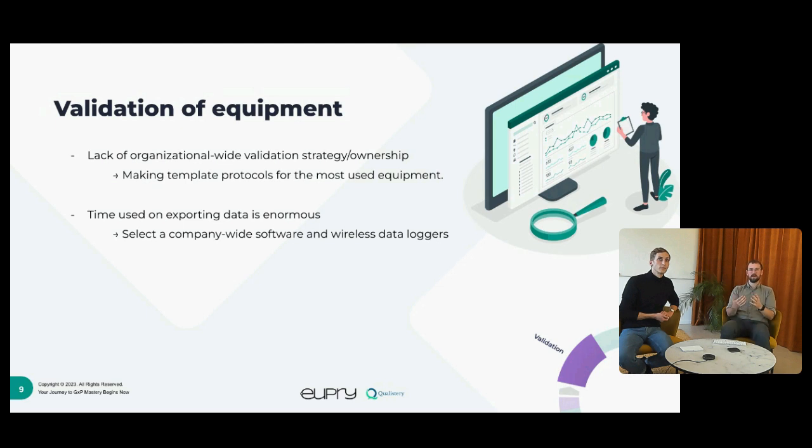I think some of the cases we see where USB loggers are being used, as an example, you'd have one-week or two-week-long studies, which you then export the data from, and you notice that it's really not in compliance, and that puts the whole project back two weeks. So having wireless data loggers is, as far as I see it in today's market, a bare minimum.